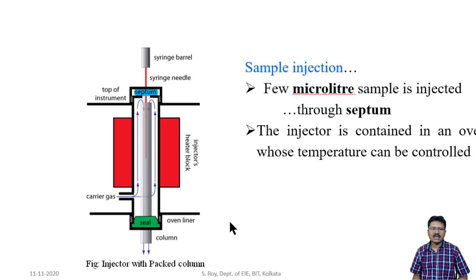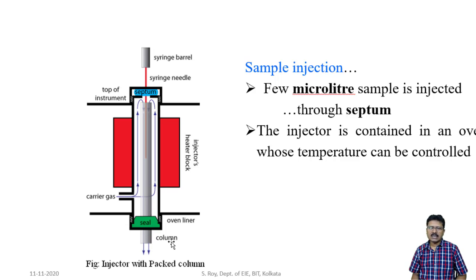A very small amount of sample is injected — normally around a microliter — through the septum using a syringe. The carrier gas carries the sample to the column. The whole sample injection part is maintained at a constant temperature normally 50 degrees higher than the highest boiling point of any component in the mixture, so that all components will be in gaseous form.